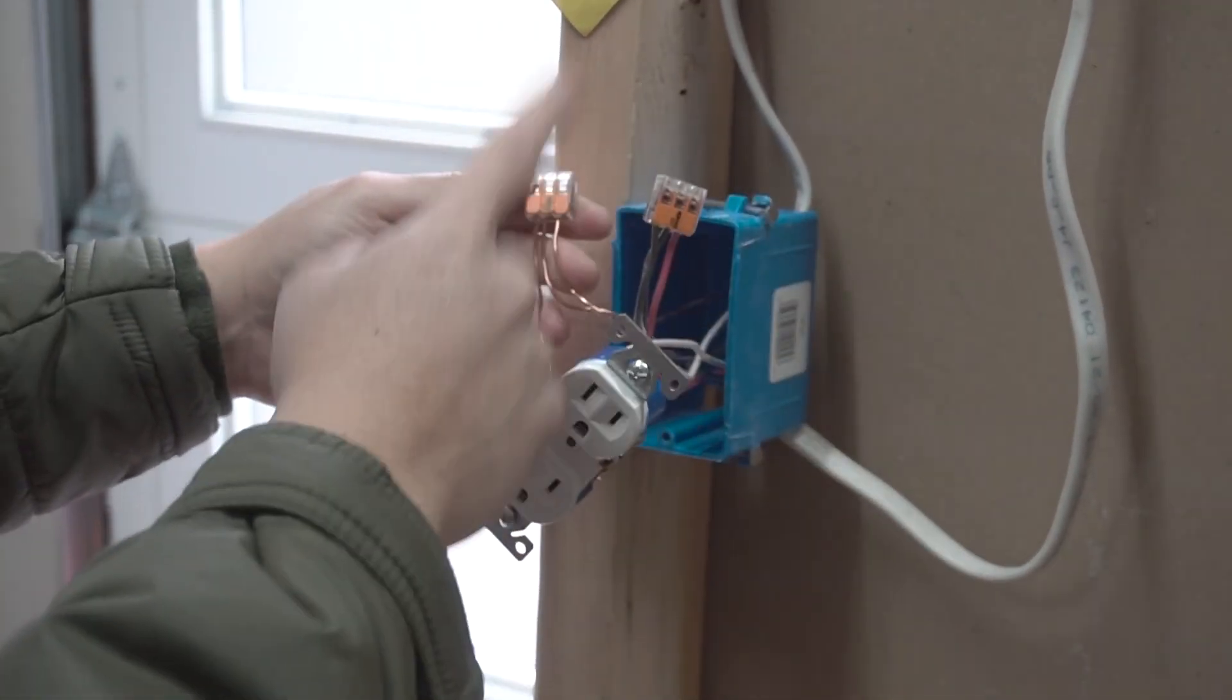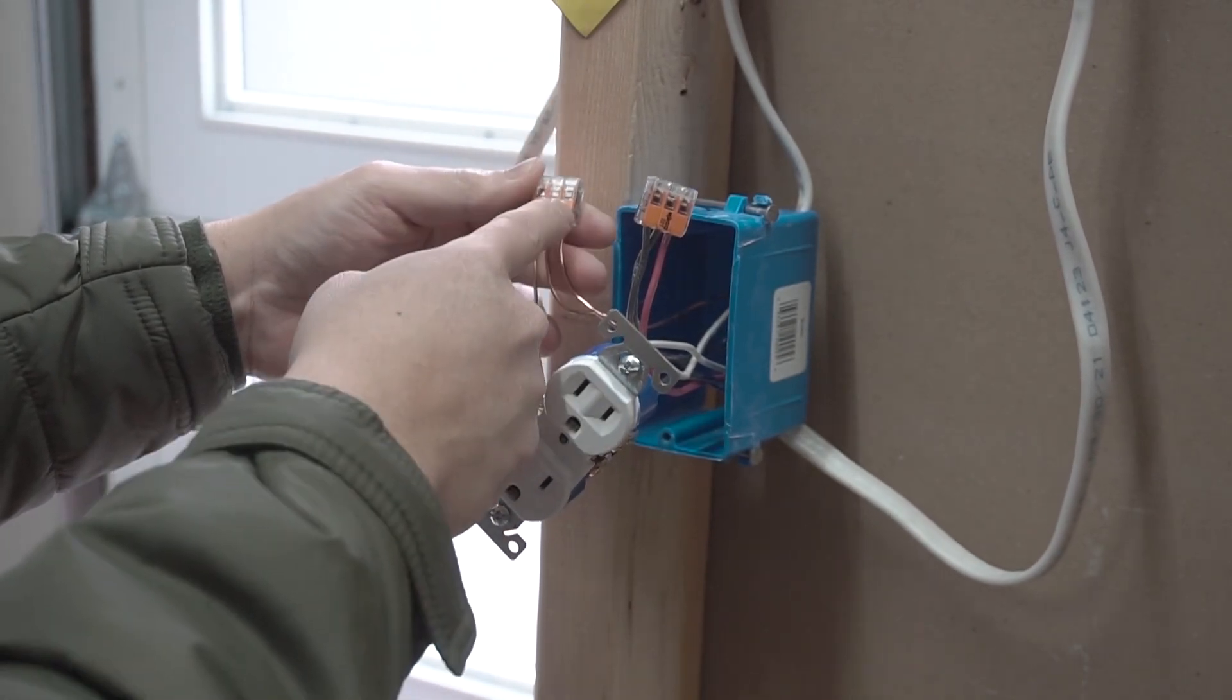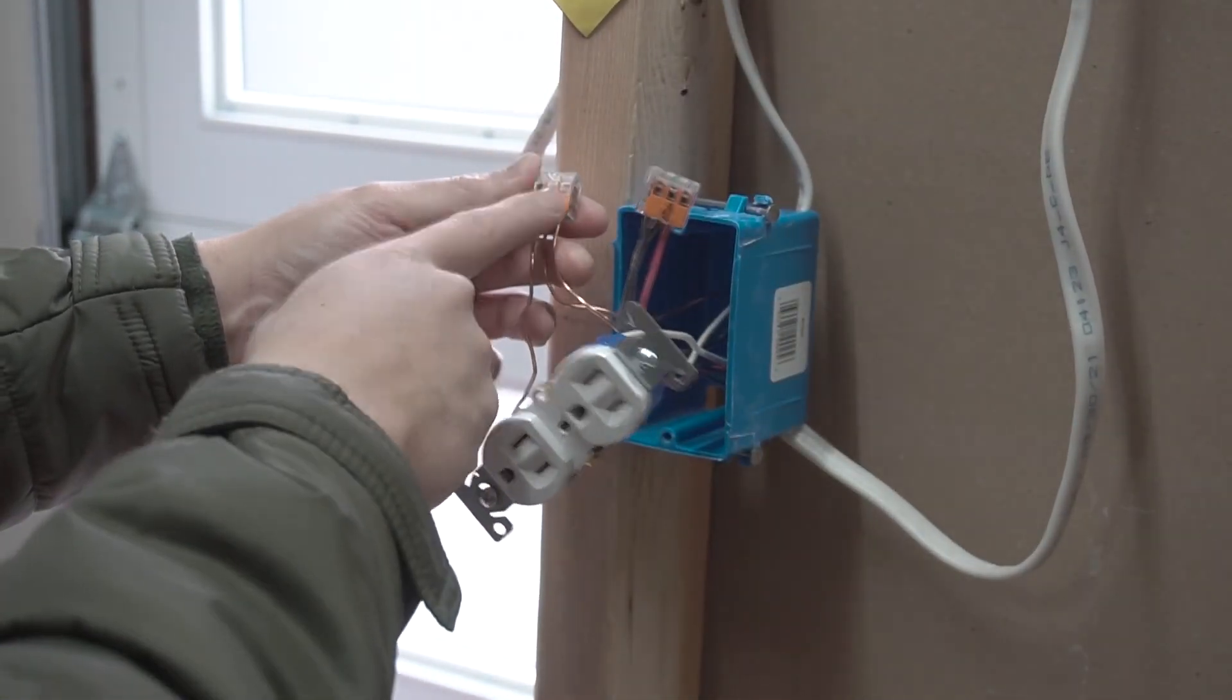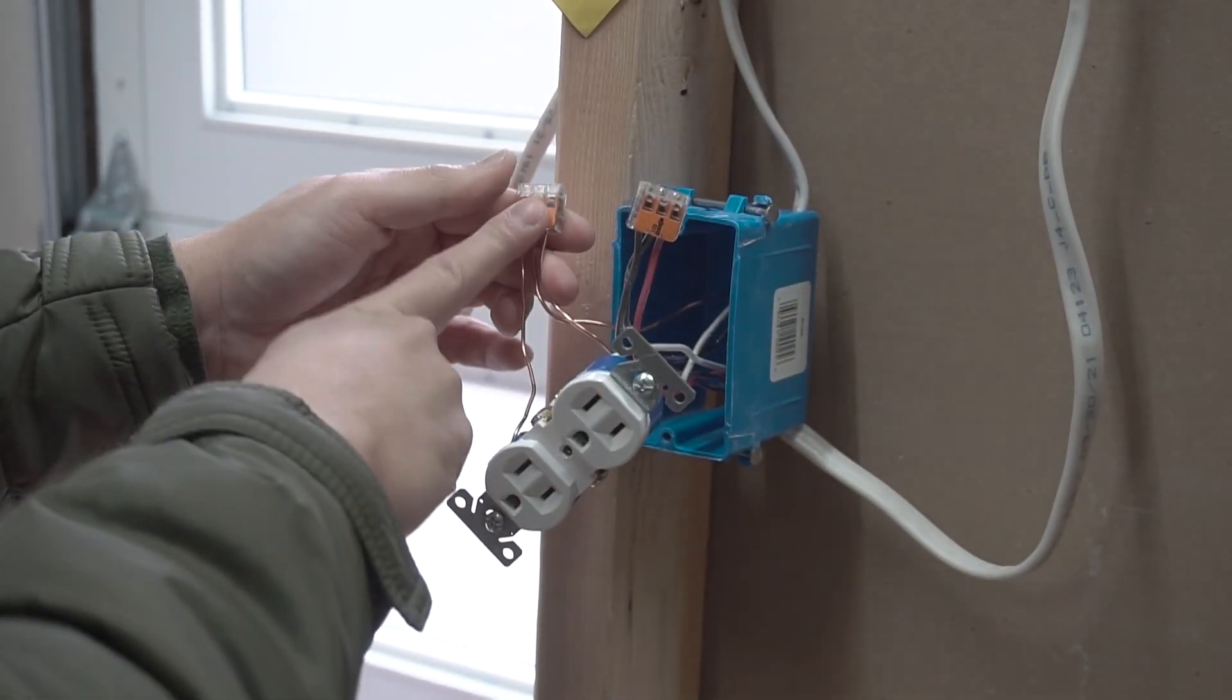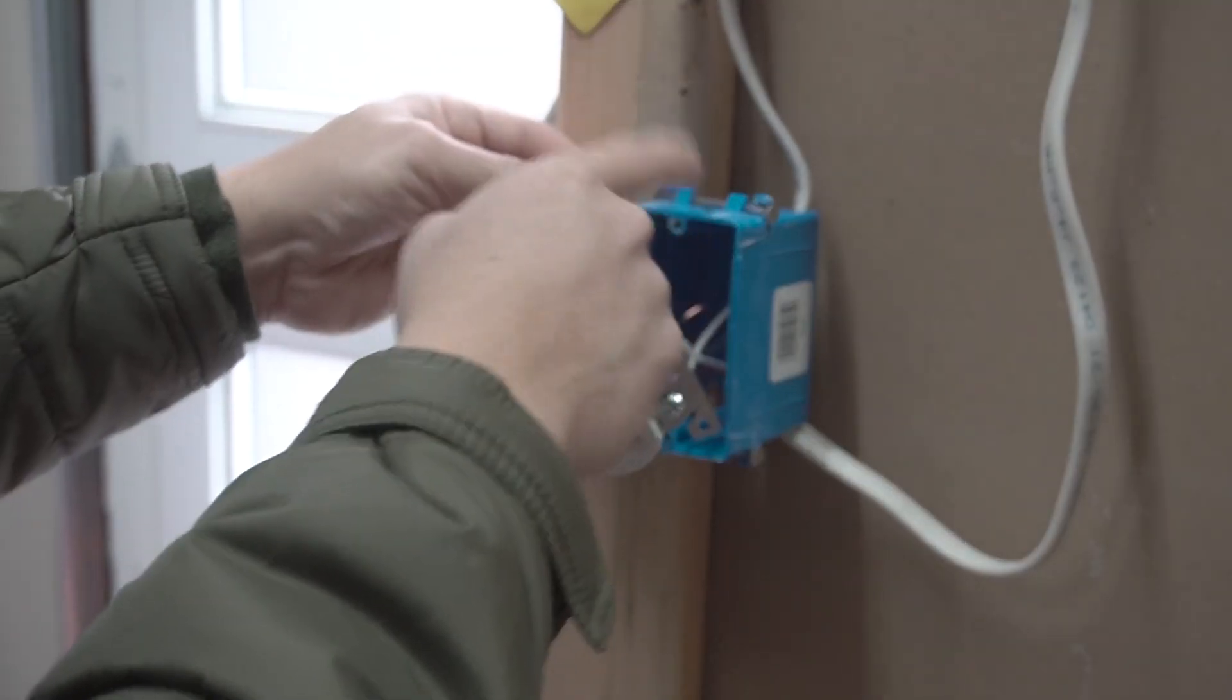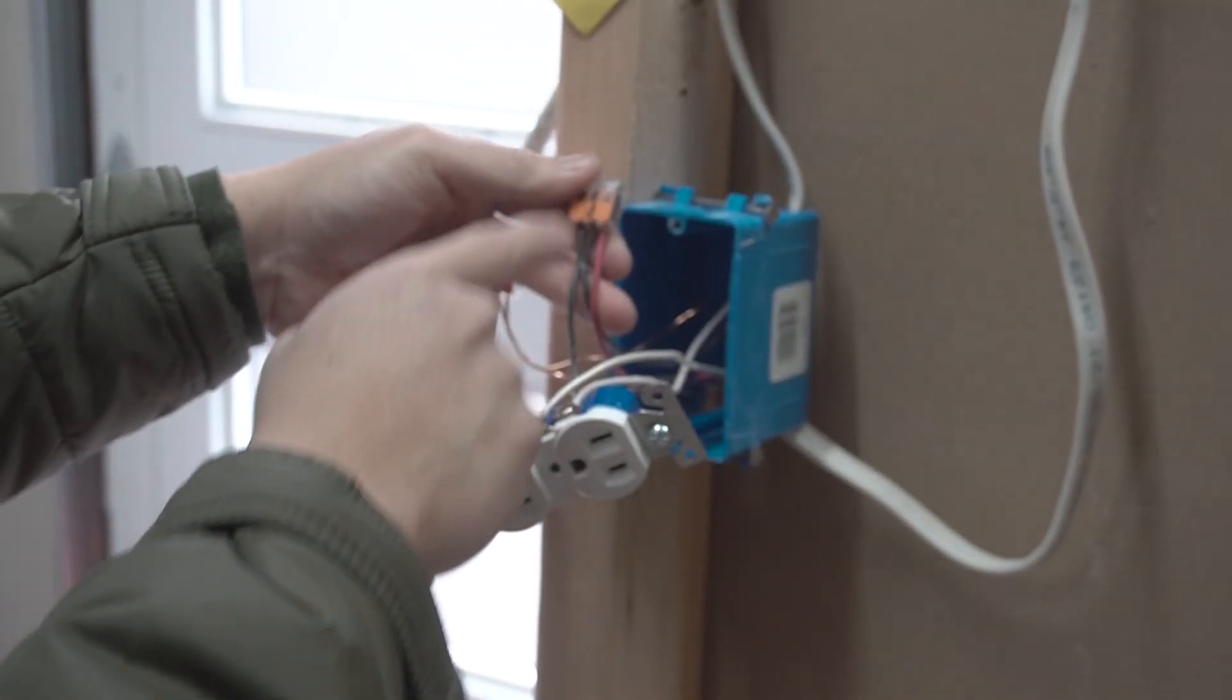Now we connected a pigtail onto the top hot screw terminal and then we connected another pigtail onto the ground terminal. Now let's start with the ground first. The ground from our 14-2 power source, the ground from our outlet, and the ground from our 14-3 is all fed into the same connector.